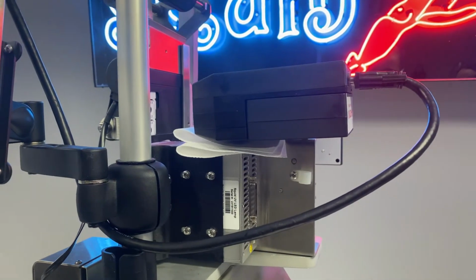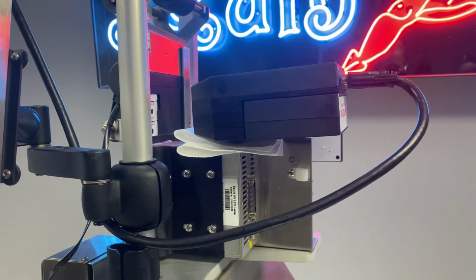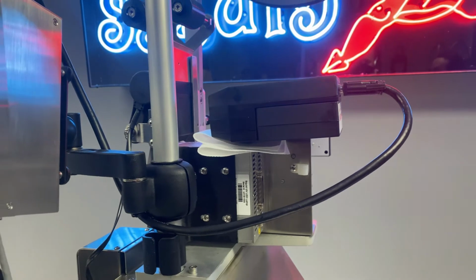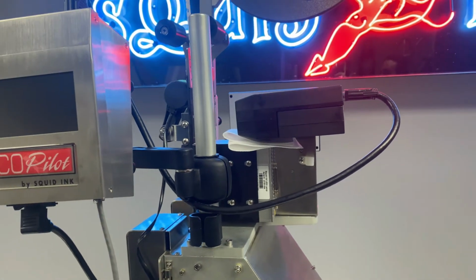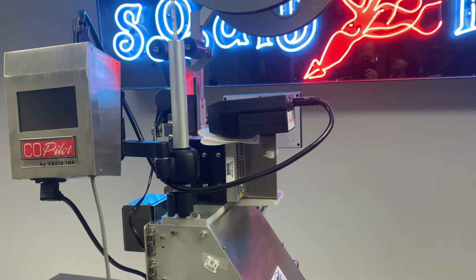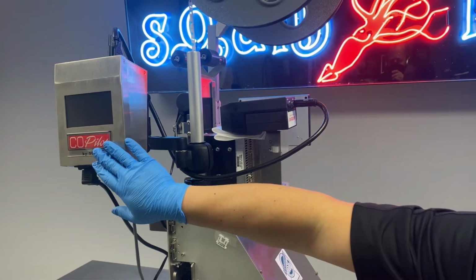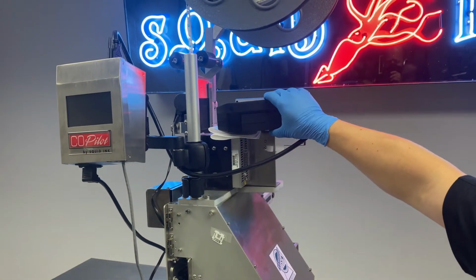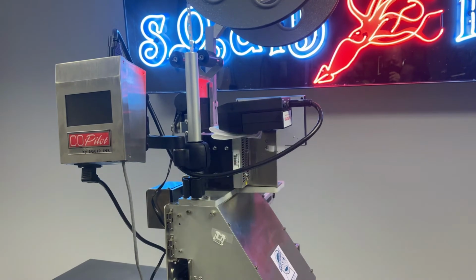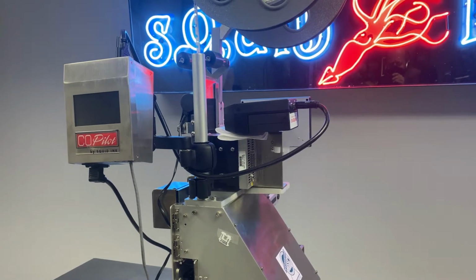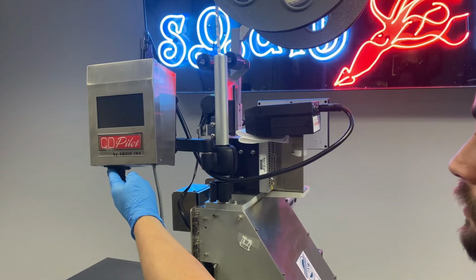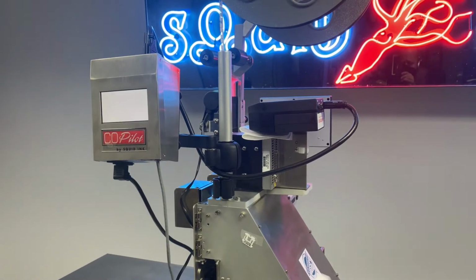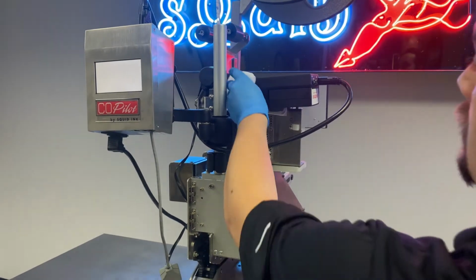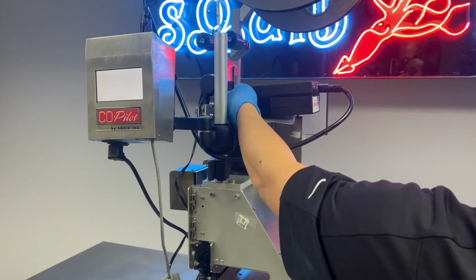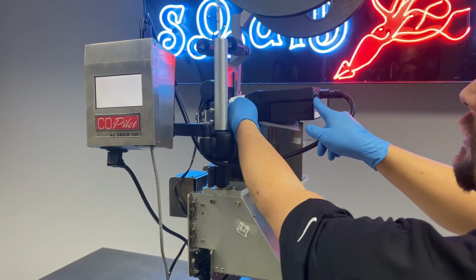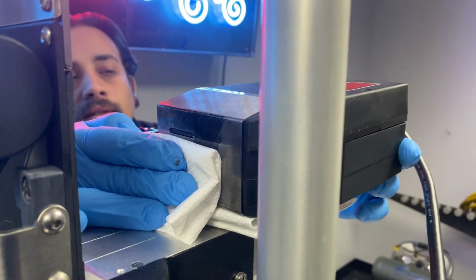Now I want to prepare another lint-free wipe to catch any ink that comes out of the print engine while we purge. What we're doing now is called the commissioning process. Notice the power is off on the controller, the printhead's in the back position, and we're ready to catch ink. At this point we turn on the power to the controller, take our lint-free wipe, hold it in front of the printhead, and press the purge button at the back of the head.